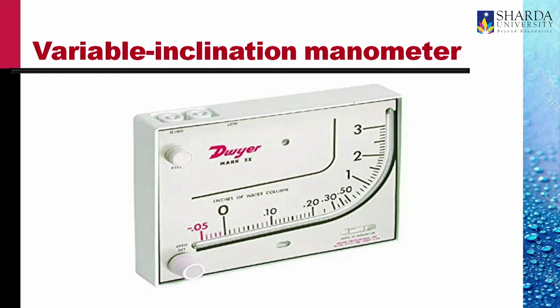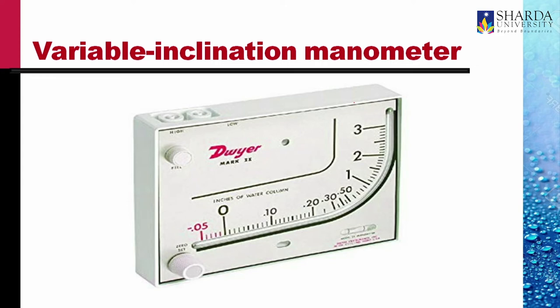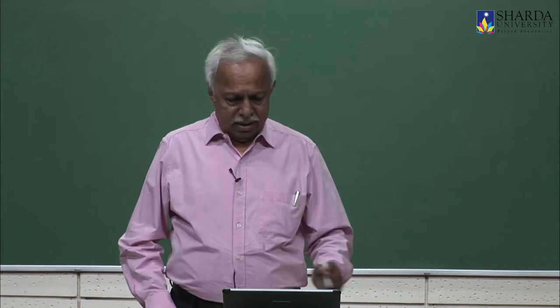This is another inclined tube manometer in which the inclination is variable. Errors in measuring very low liquid heights are large compared to errors in larger heights. So we need more inclination when the height of the column is less, but we can do with lesser inclination when the height is more. In this commercially available variable inclination manometer, the tube is curved such that the inclination at low values of head difference is large, but the inclination at higher values is low. In fact, the tube becomes vertical towards the higher end.